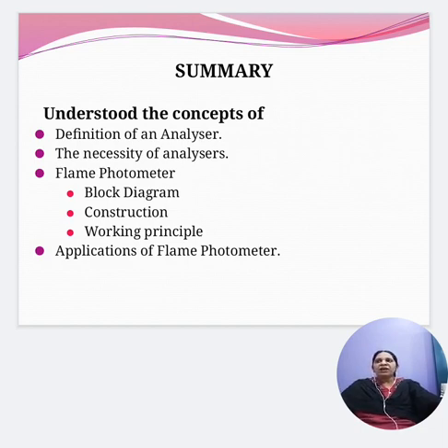So the wavelength of the color of the flame gives you the qualitative analysis of the sample or the element, and the concentration of the sample, that is nothing but quantitative analysis, is done by measuring the intensity of the light, intensity of the color. So under constant controlled conditions, the light intensity of the characteristic wavelength produced by each of the atoms is directly proportional to the number of atoms that are emitting the energy, which in turn is directly proportional to the concentration of the substance of interest.